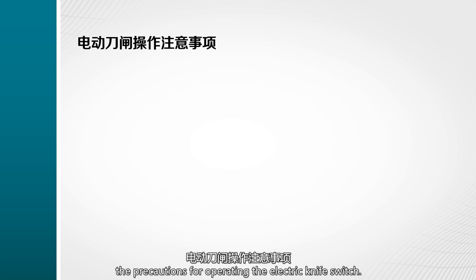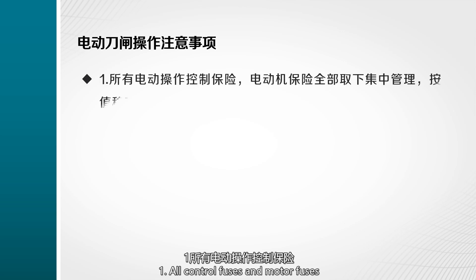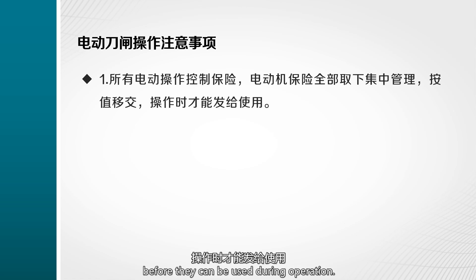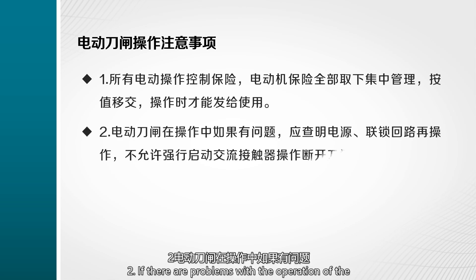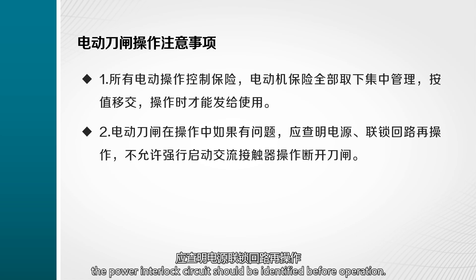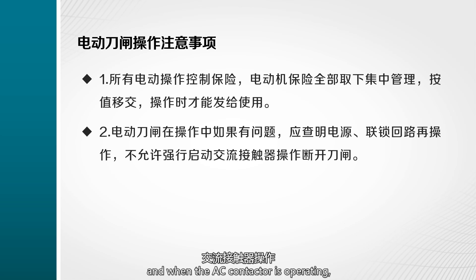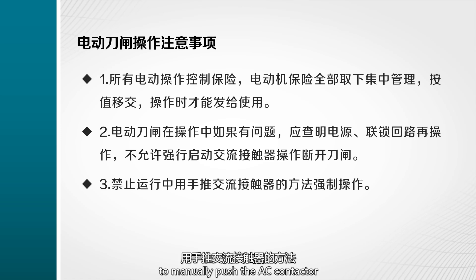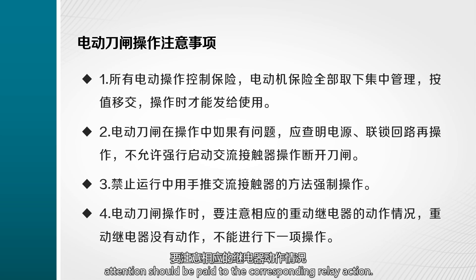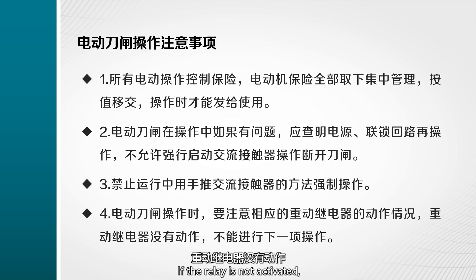Precautions for operating the electric knife switch: First, all control fuses and motor fuses for electric operation should be removed, centrally managed, and handed over according to their values before use during operation. Second, if there are problems with the electric knife switch operation, the power source and interlock circuit should be identified before proceeding — forceful starting is not allowed when the AC contactor is operating. Third, it is prohibited to manually push the AC contactor during operation to force running. Fourth, when operating the electric knife switch, attention should be paid to the corresponding relay action; if the relay is not activated, the next operation cannot be carried out.